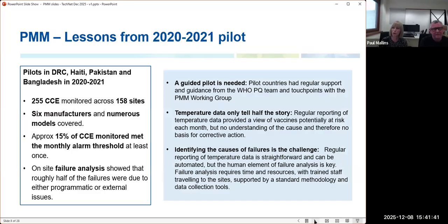Just to give you a little bit more background from the pilot that we did a few years ago. We did a pilot in 4 countries: DRC, Haiti, Pakistan, and Bangladesh. This was more than 250 fridges that we monitored over 1 year. What we found was that about 15% of the cold chain equipment did meet one of these monthly thresholds at least once during the year.